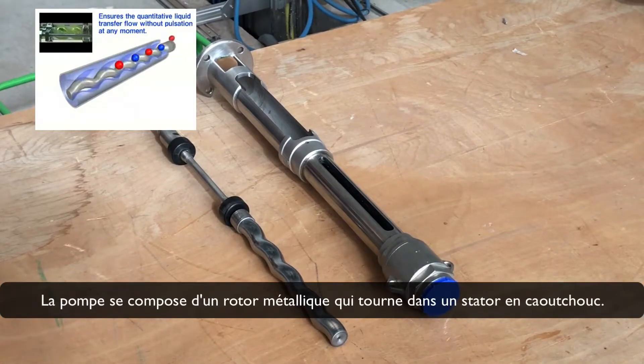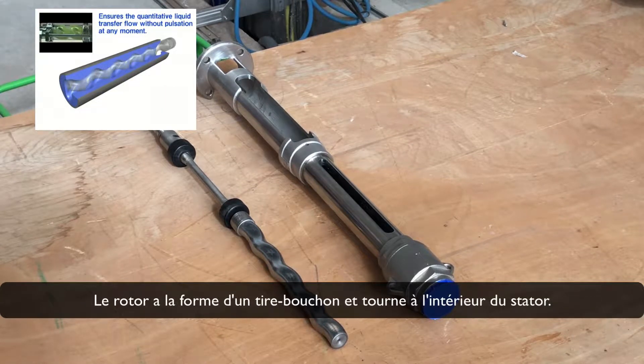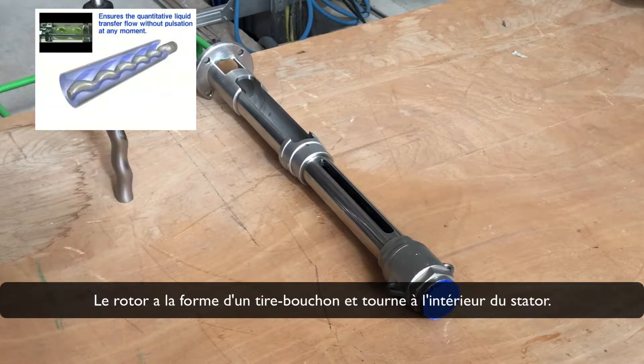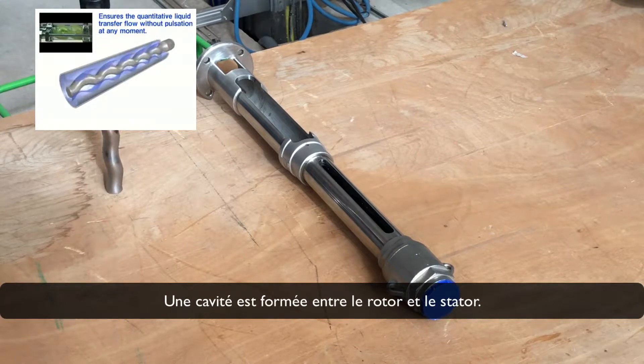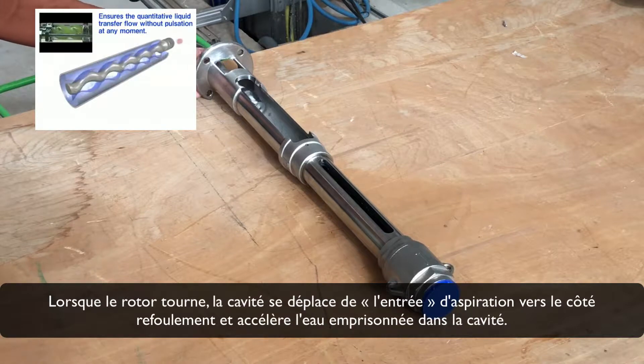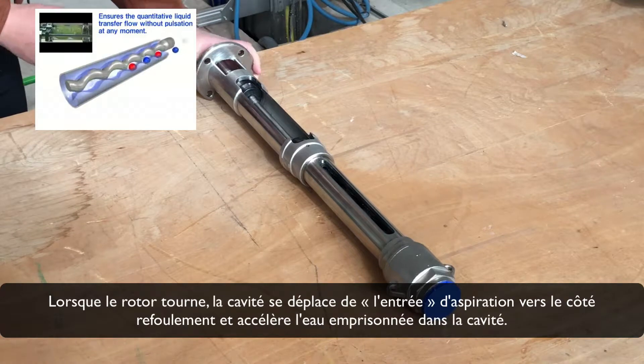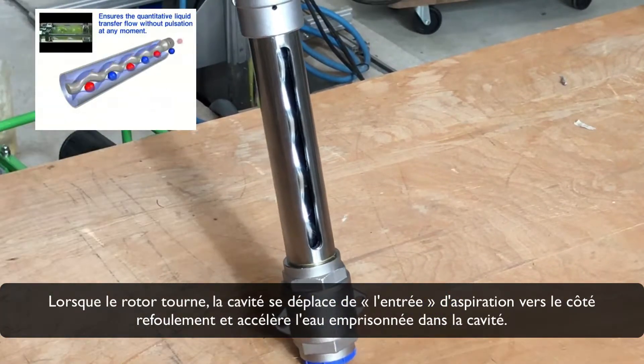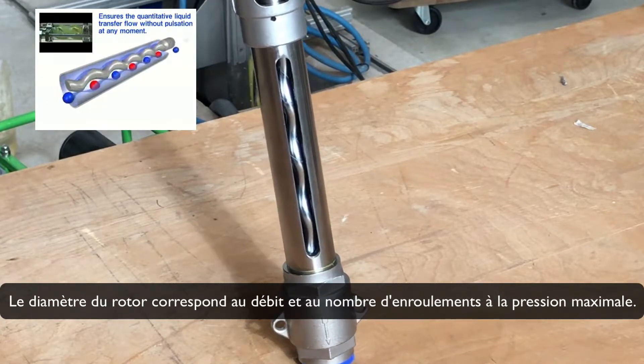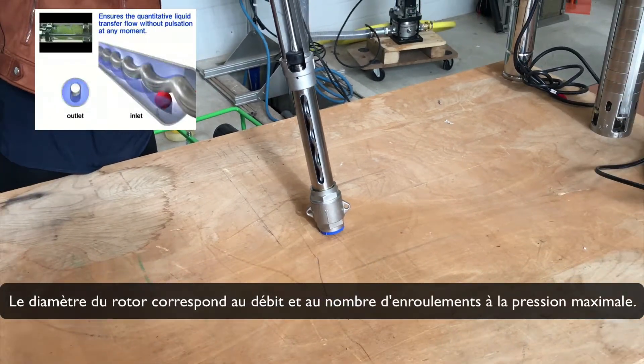The pump consists of a metal rotor which turns inside a rubber stator. The rotor is shaped like a corkscrew and rotates inside the stator. A cavity is formed between rotor and stator. As the rotor turns, the cavity moves from the suction inlet to the pressure side and accelerates the water locked in the cavity. The diameter of the rotor corresponds to the flow rate, and the number of windings to the maximum pressure.